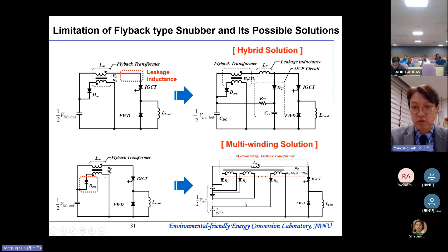This photo shows the experimental setup in our lab. This is the IGCT stack for the 3-level NPC, this is the flyback type transformer, and this is the DC link cap. We're doing the single pulse test with an inductive load. For the single pulse test we usually perform a double pulse, because we like to do turn-on while the current has not yet recovered to zero.